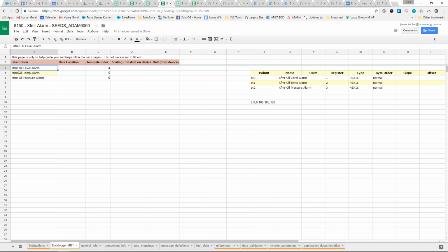So we're saying here, oil level alarm is index 4. When this is sending 100 on 4, that corresponds to the oil level alarm, right? The next one, index 5, is the temperature alarm, so that's also 100 in my terrible example. Same thing for pressure alarm. Index 6 is also 100, right? So in other words... Quick question.